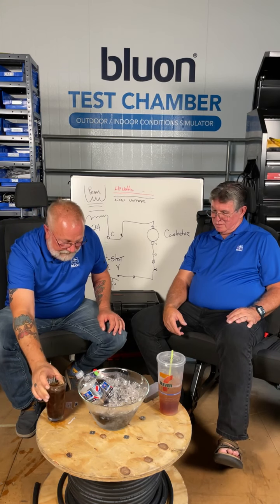Because to turn around and bypass a board, you know, it's 95, 100 degrees outside, and it's going to get down to 85 at night. To bypass a defrost control board, I could care less, right? Because I don't have to worry about flooding back or tearing up the compressor or turning the condensing unit into a block of ice. I'm good with that. But if you need the defrost and everything else, it's not a good idea, because you went from replacing a $500 board to replacing a $2,000 or $3,000 compressor, and that gets kind of hard to swallow sometimes. So just ask yourself that question.